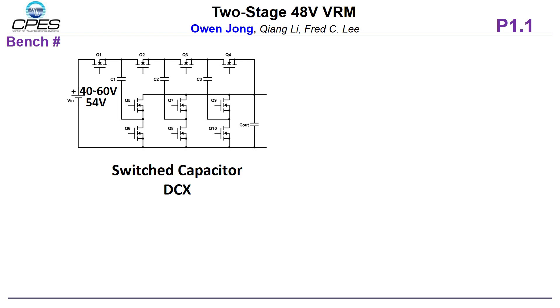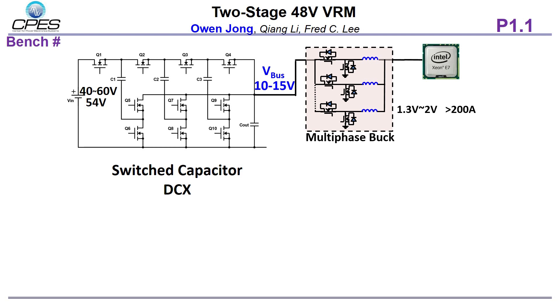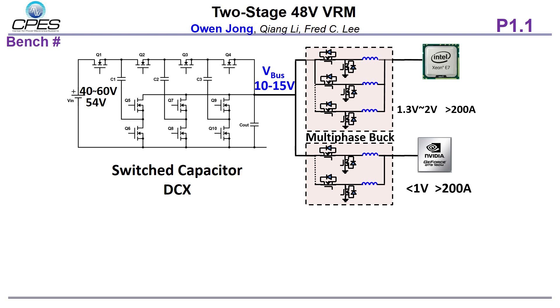This figure shows the two-stage architecture for the 48-volt VRM. The first stage is an unregulated switched capacitor converter with a conversion ratio of 4 to 1, which gives a 10 to 15-volt bus voltage. The switched capacitor converter largely reduces the magnetic components and improves power density. Multiple point-of-load bus converters then supply different loads such as CPU, GPU, and DDR.